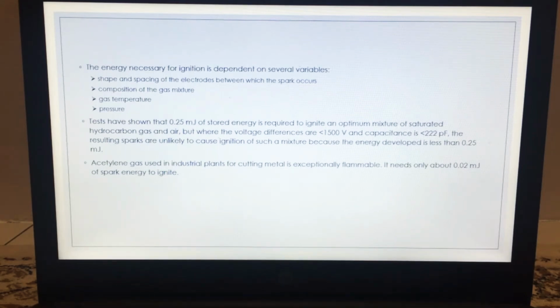Tests have shown that 0.25 millijoule stored energy is required to ignite an optimum mixture of saturated hydrocarbon gas and air. But where the voltage differences are less than 1500 volt and capacitance is less than 222 picofarad, the resulting sparks are unlikely to cause ignition of such a mixture because the energy developed is less than 0.25 millijoule. Acetylene gas used in industrial plants for cutting metal is exceptionally flammable. It needs only about 0.02 millijoule of spark energy to ignite.